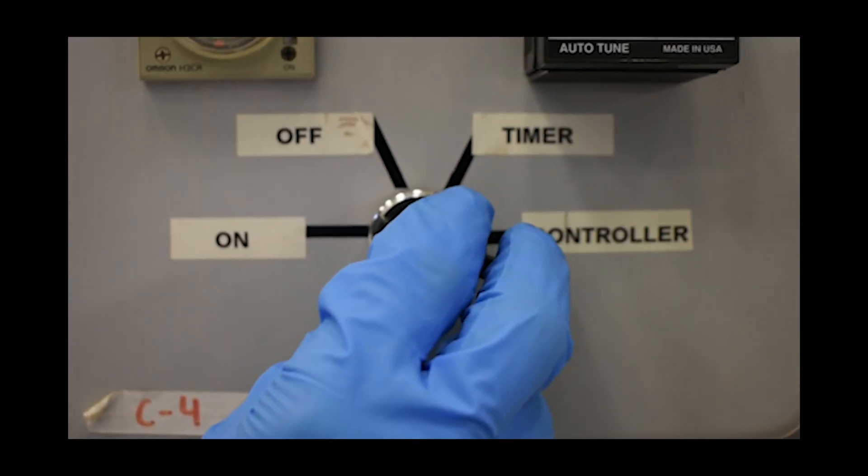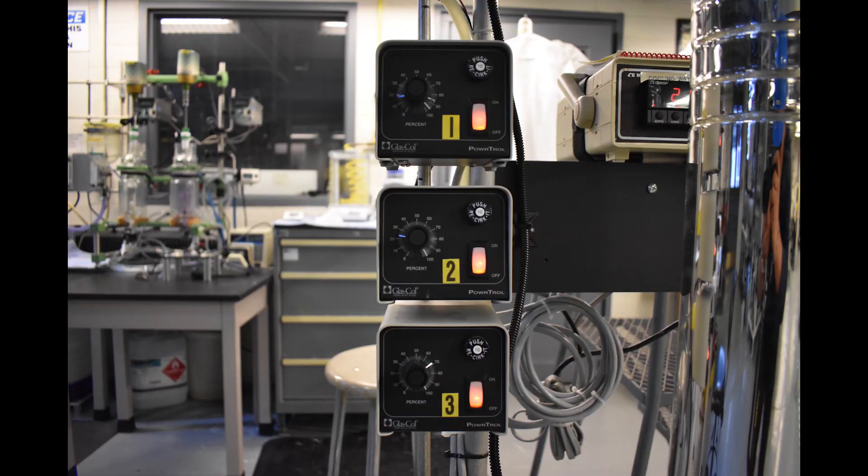Before turning on the heaters, make sure the column is going to be operating at total reflux by setting the control panel to off using the dial on C4. Now you can turn on the heaters.